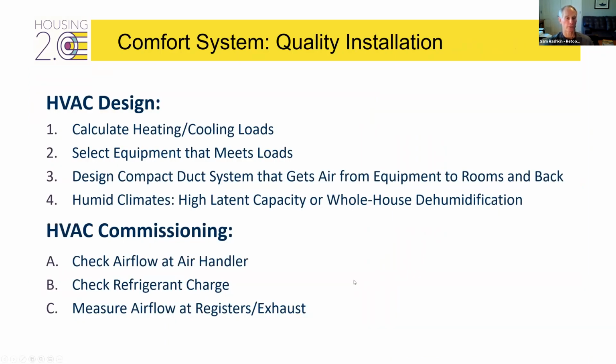The Energy Star program has a great protocol for quality installation. Now the HERS RESNET program has quality installation integrated in the score that you achieve. But it's the basics: you've got to design the system and the loads, select equipment that meets the load requirements, design the duct, and enforce the installation to that design in the field. And in humid climates, you have to have solutions for high latent capacity because you're now in a high performance enclosure. You can integrate it with variable speed equipment or have a dedicated whole house dehumidifier.